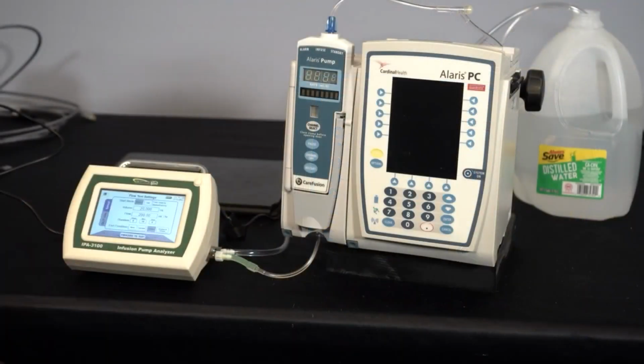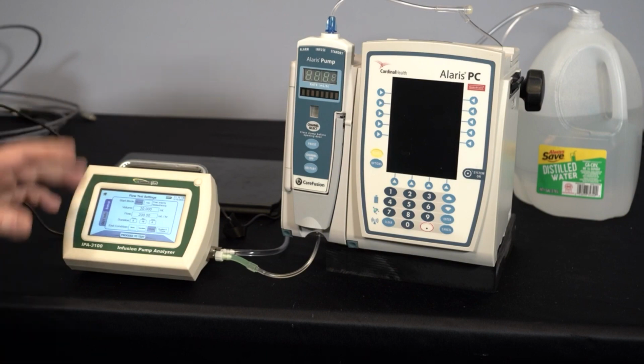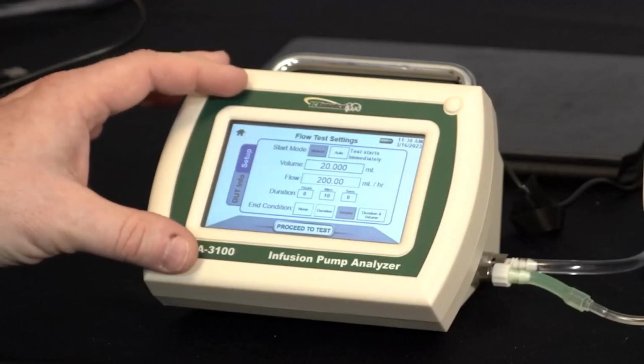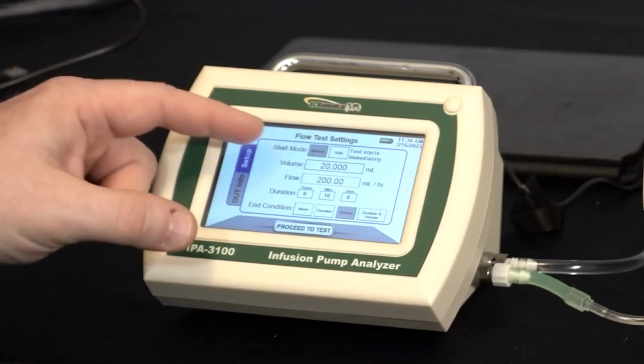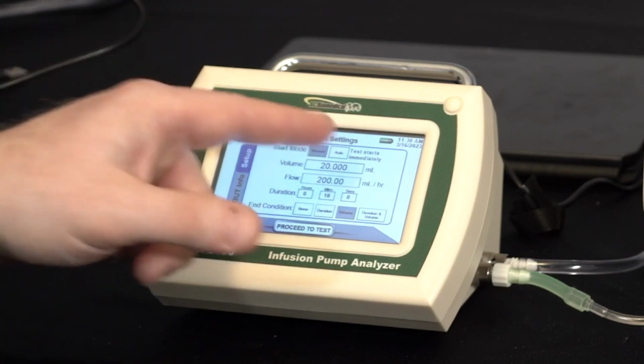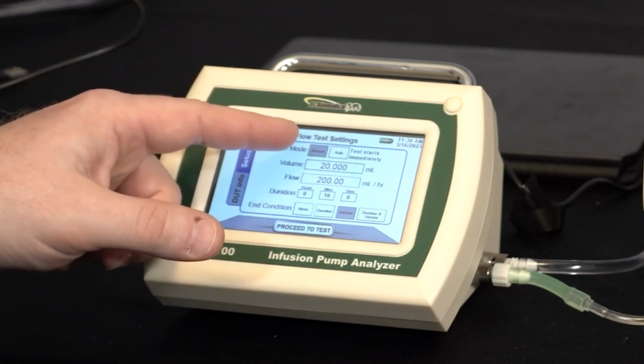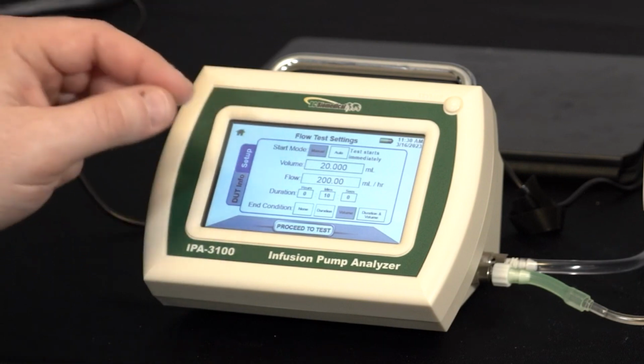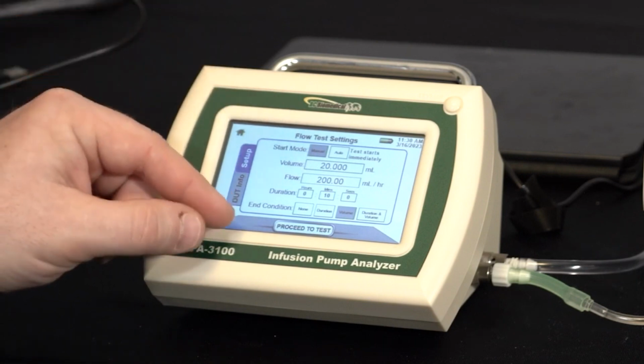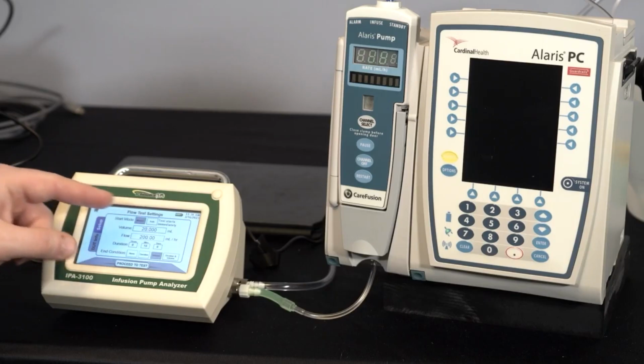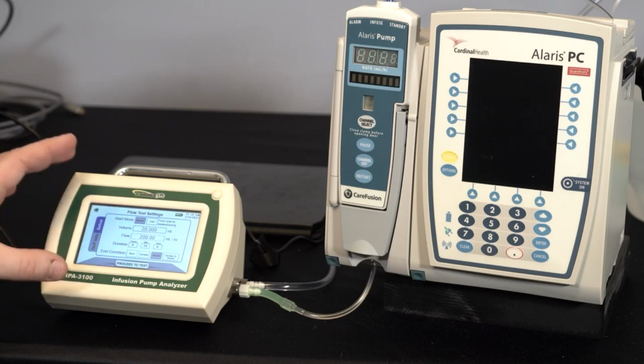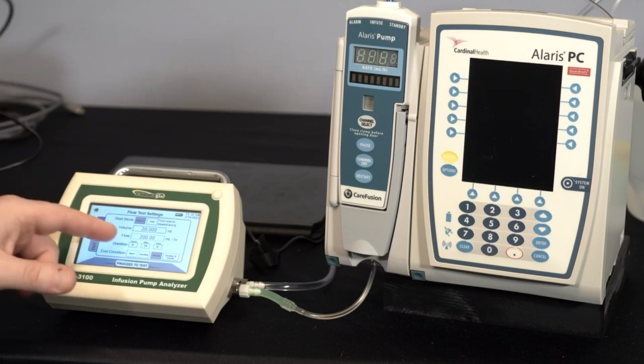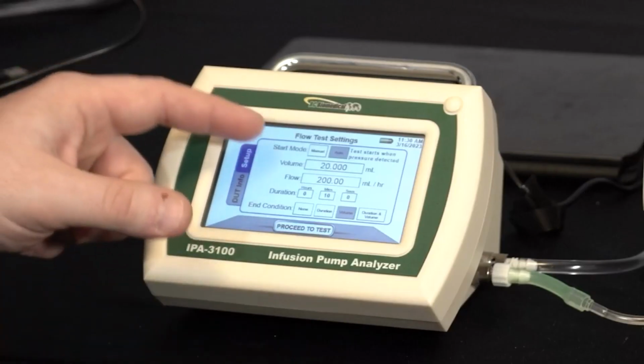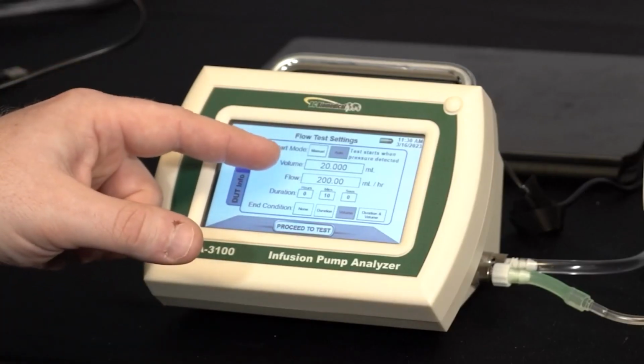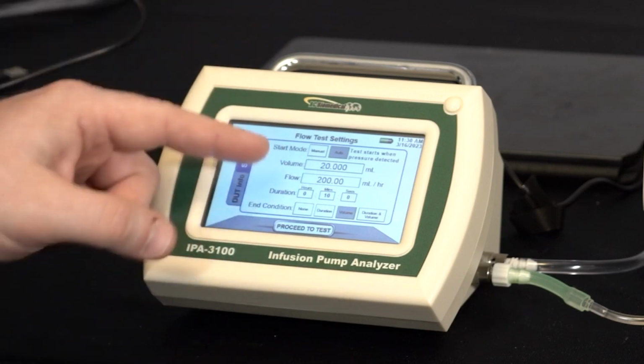Now we go to flow test, and this shows us the configuration for the flow test that we're going to run. We can pick a start mode, which is either manual or auto. The manual will start the test immediately when I hit start on the analyzer. Auto, I can start the test and it won't actually start counting time until it detects flow. That makes it more automated for me. So I'm going to go ahead and select auto. The volume is how much volume we're expecting to deliver.